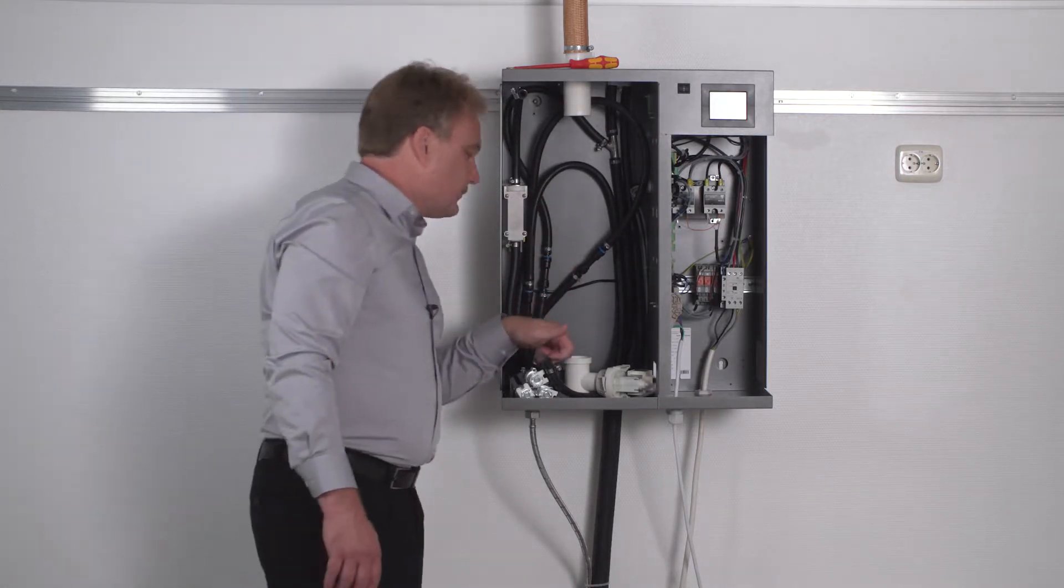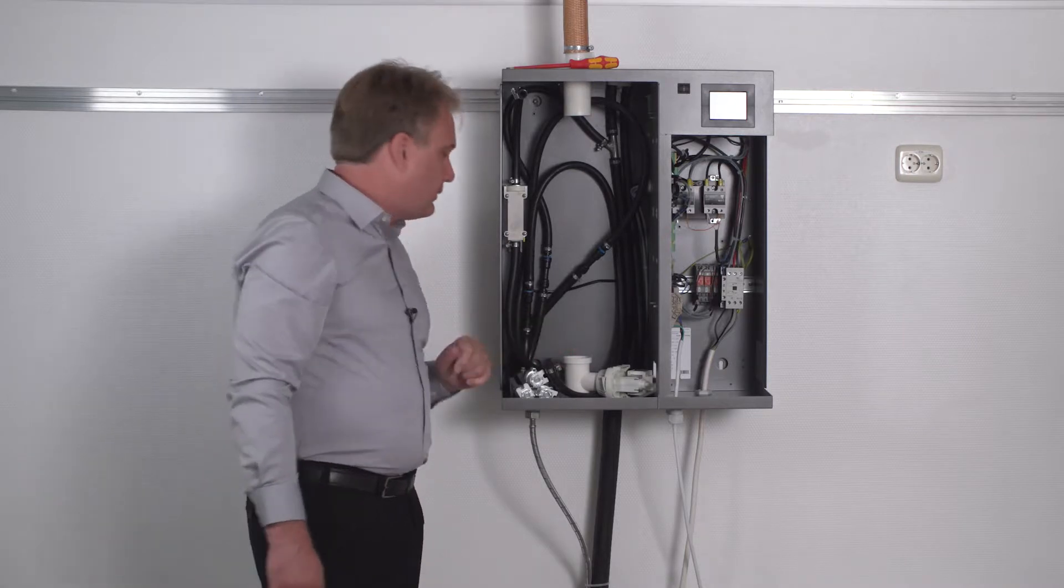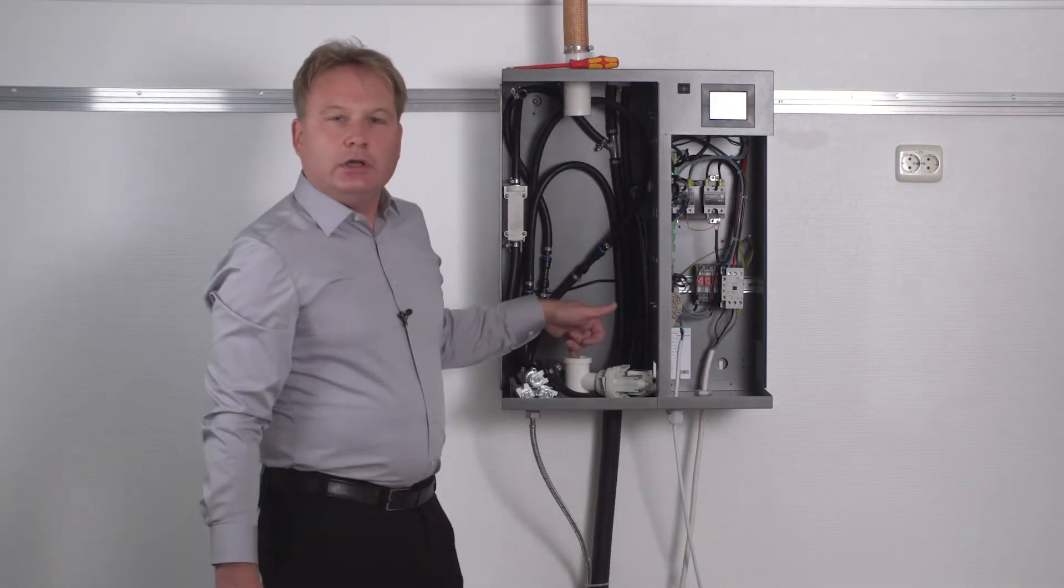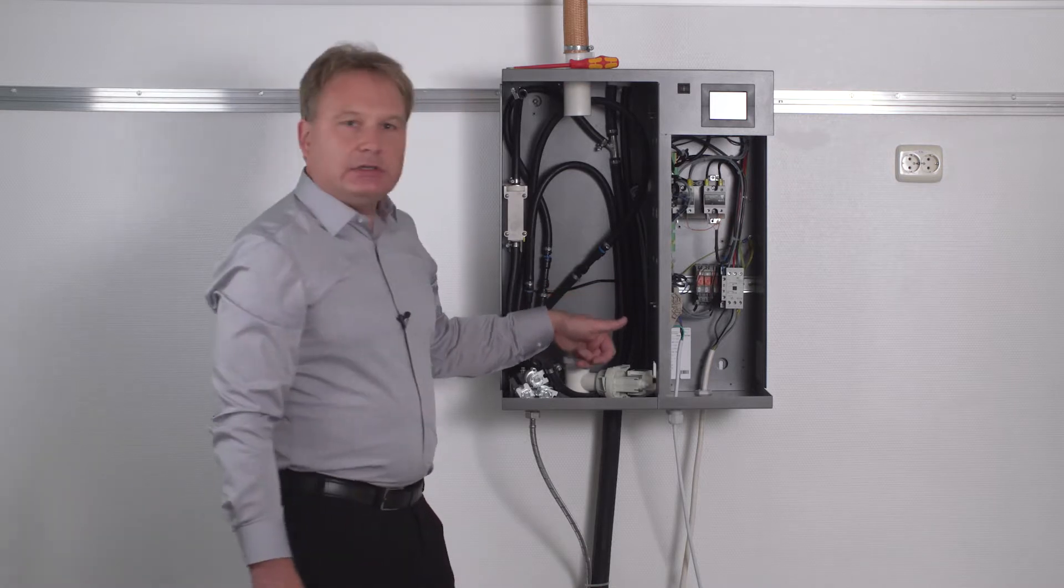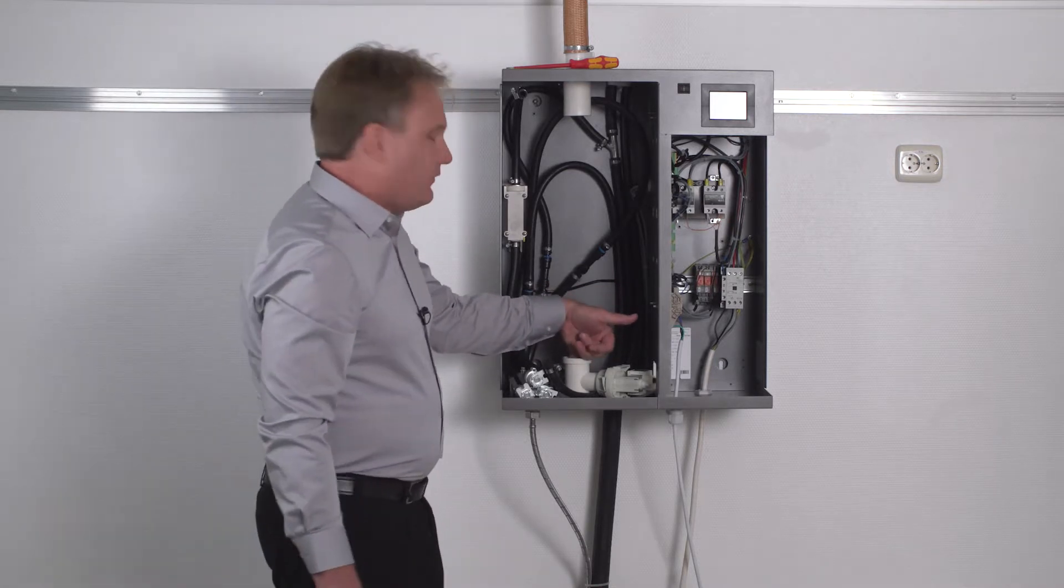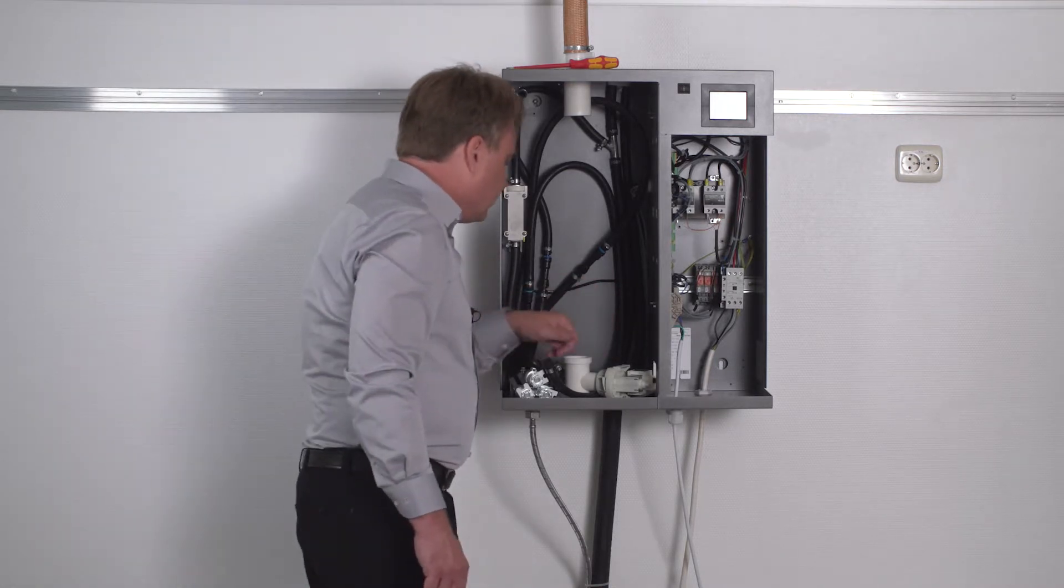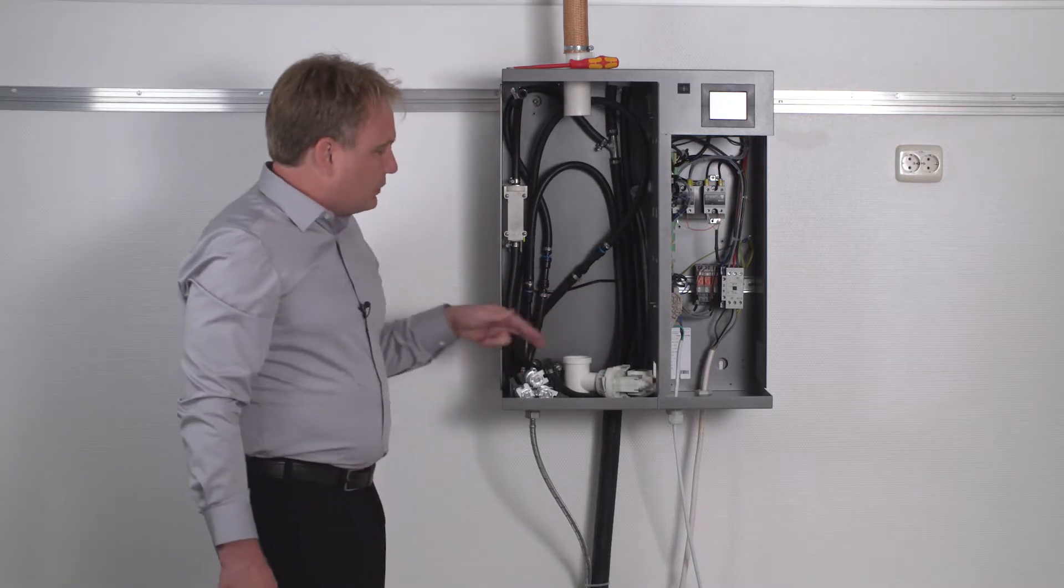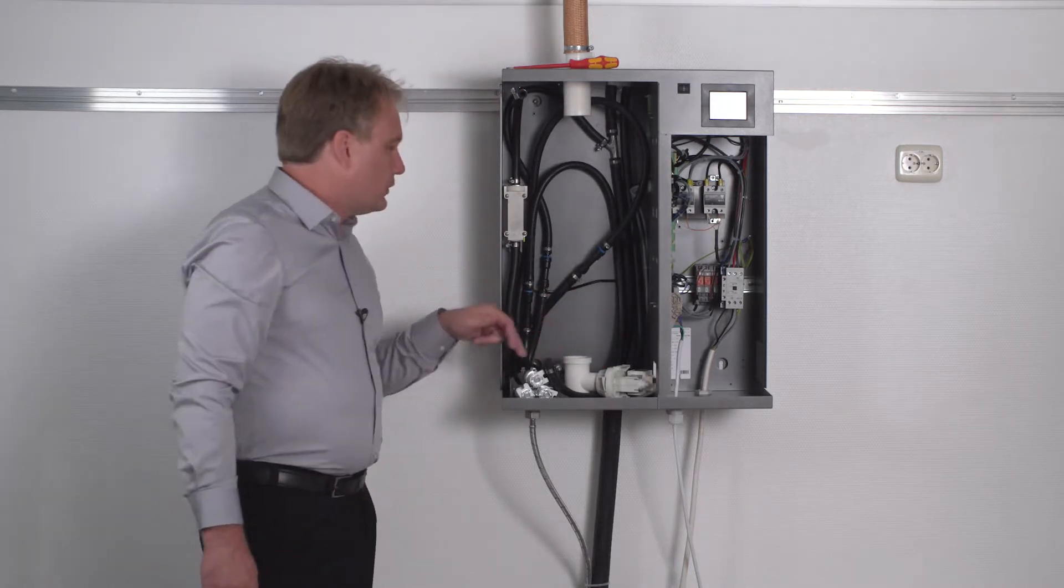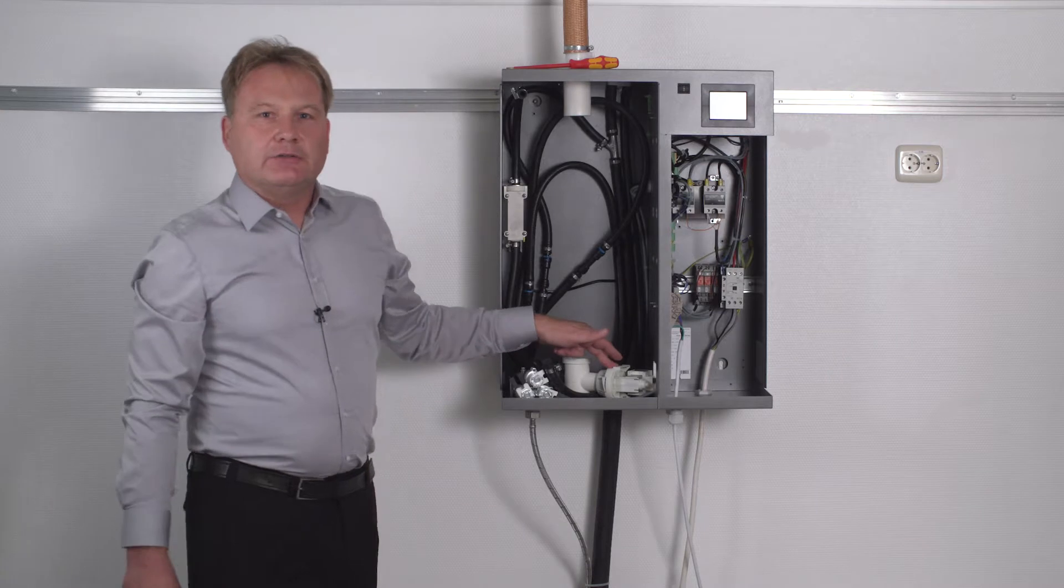Next, I look into the cylinder base, whether mineral deposits have formed in the base and have to be removed. If this is the case, the cylinder base will have to be dismantled and the blowdown pump must be cleaned.